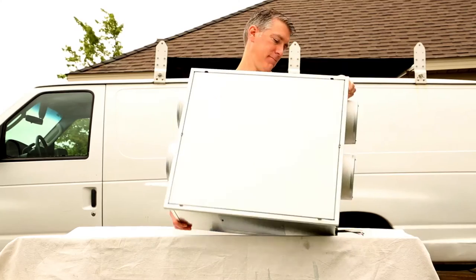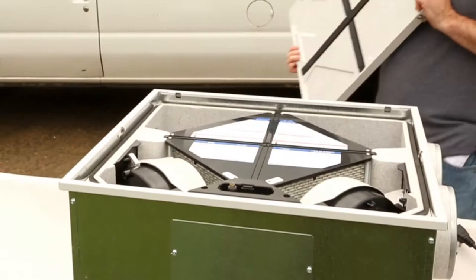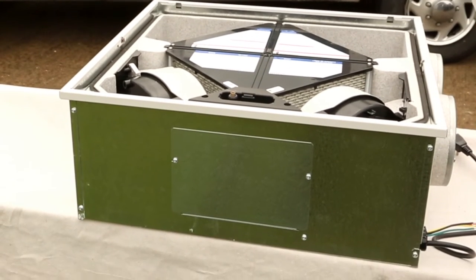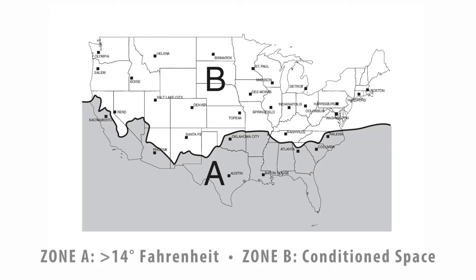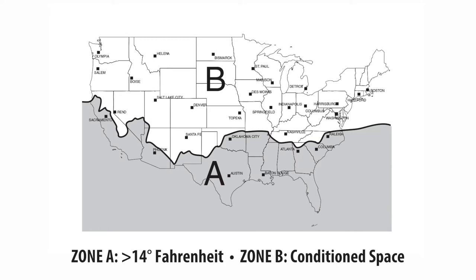The ERVS-100 is designed for installation where temperature is above 14 degrees Fahrenheit throughout the year, or Zone A on this map. Units installed in Zone B must be installed in a conditioned space.